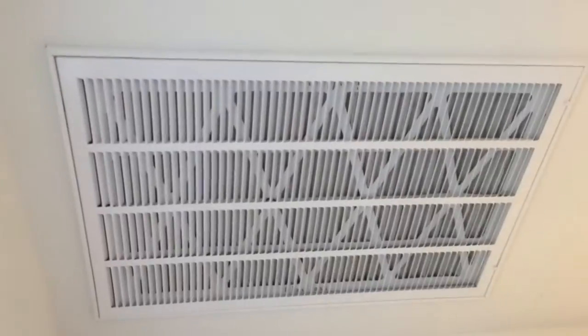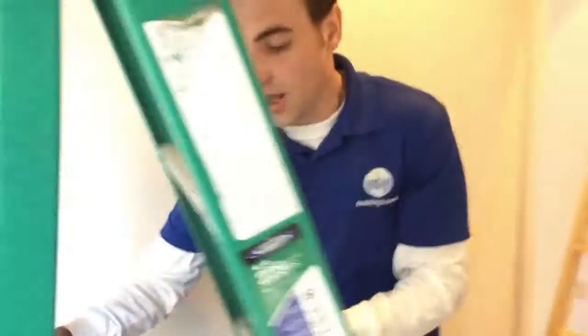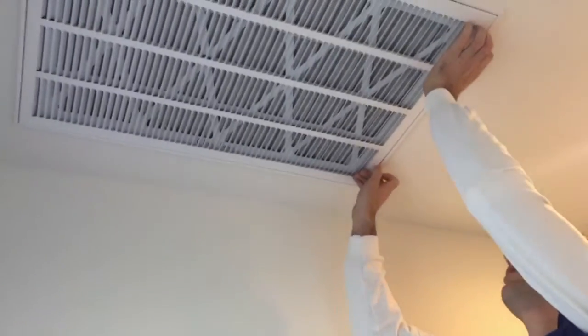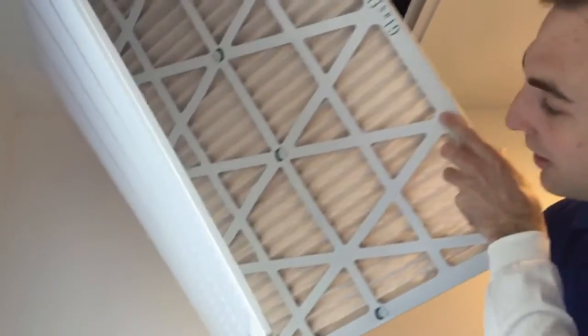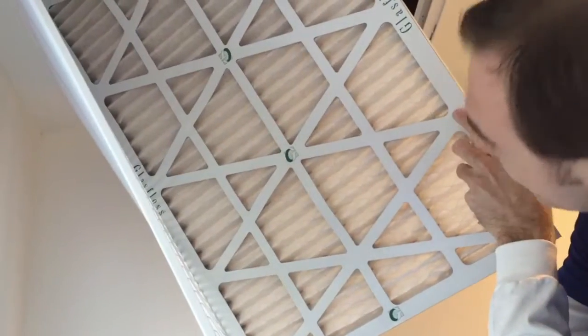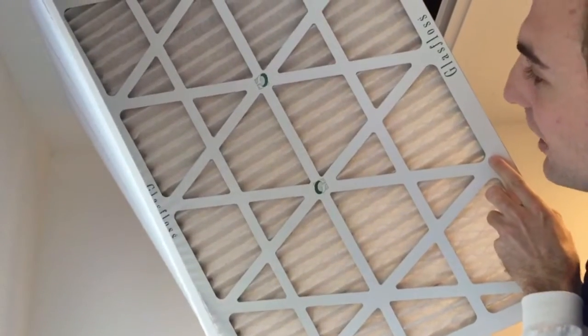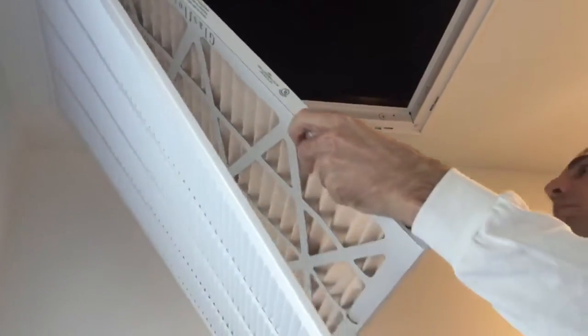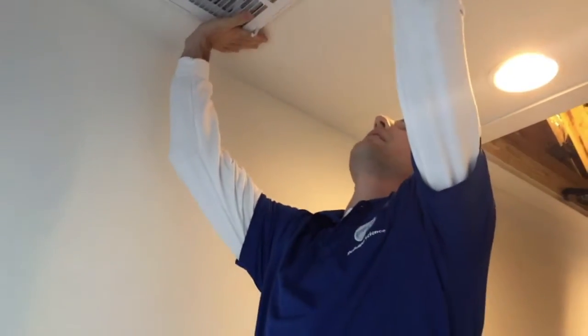One of the things we're going to want to look at before we test the airflows is the filter. We want to make sure that the air filter is not full of dust, because if it is, it's going to hurt the amount of airflow that comes out of the supply vents. So this filter's pretty new, pretty good. You can sort of see the light through it. If it were really bad, we would then take it out before testing.